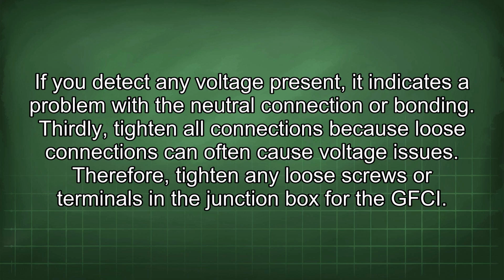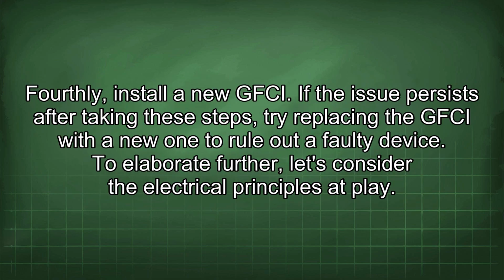Thirdly, tighten all connections because loose connections can often cause voltage issues. Therefore, tighten any loose screws or terminals in the junction box for the GFCI. Fourthly, install a new GFCI. If the issue persists after taking these steps, try replacing the GFCI with a new one to rule out a faulty device. To elaborate further, let's consider the electrical principles at play.